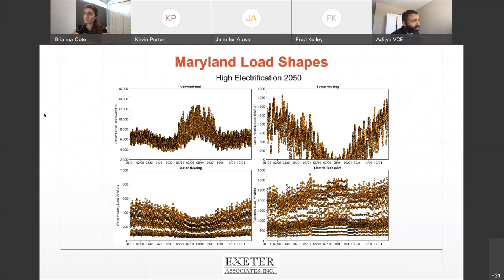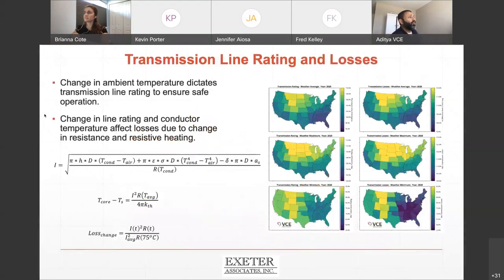We also incorporate dynamic line rating on the transmission system, as well as losses. The dynamic line rating is calculated assuming that transmission lines are designed based on the local weather and climate. Once we have the average design from that, we can figure out the additional ampacity that can be squeezed through these lines depending on local weather.